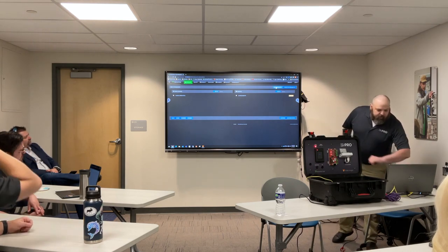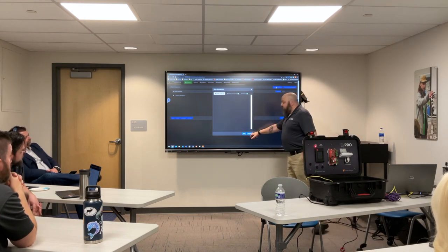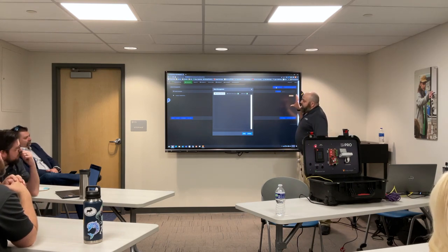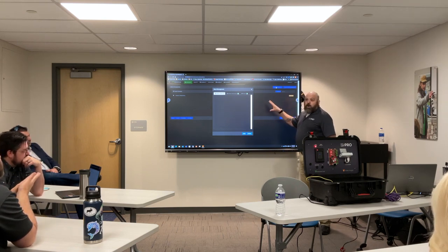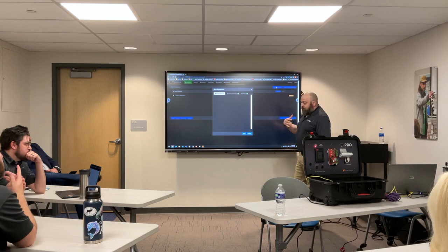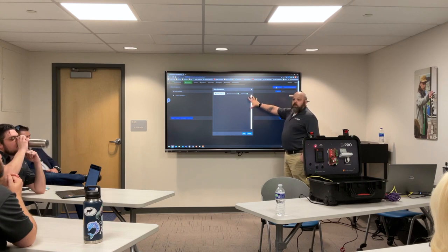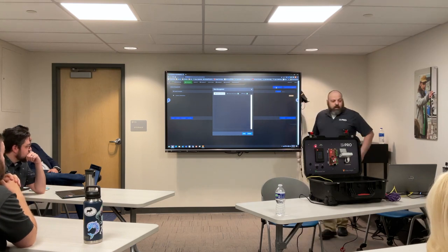This is where we're going to be able to take the monitor points, I don't have any set up, and interact with them and mask or unmask. I worked with a school in Pennsylvania. What they had was, during instruction time, if one of the exterior doors was open, they wanted a sounder to go off, and then in VI, our VMS platform, a live window pop-up to come up on the secretary's desk. And then in between periods, the students were allowed to leave and come back in, so we would mask the door position switches at that time, and then unmask them whenever it was an instructional period. So that's something that we've also accomplished.